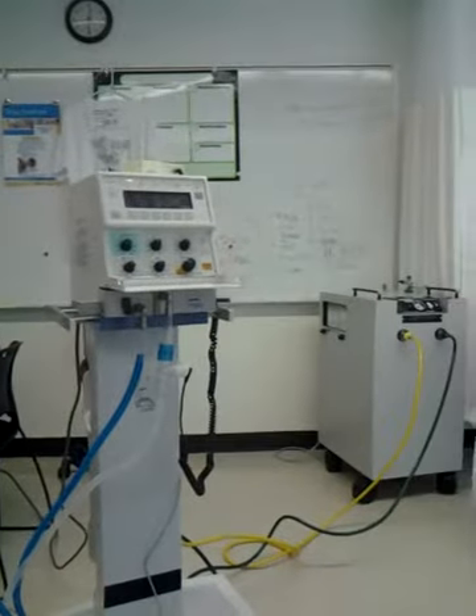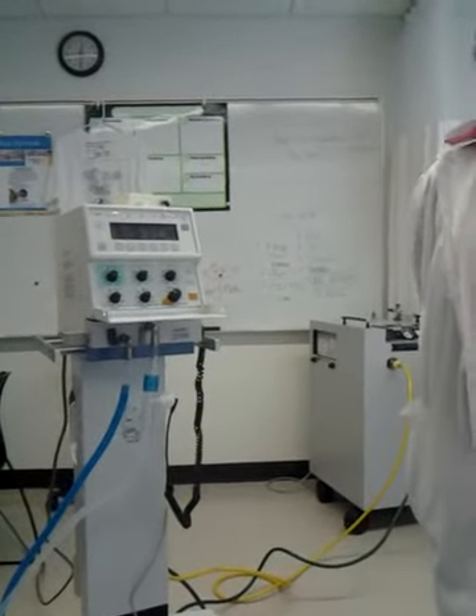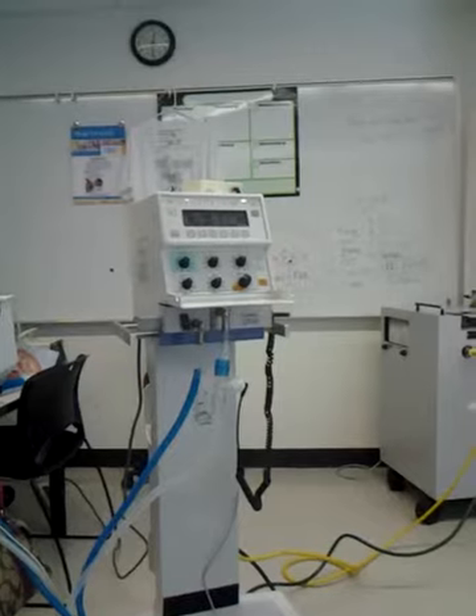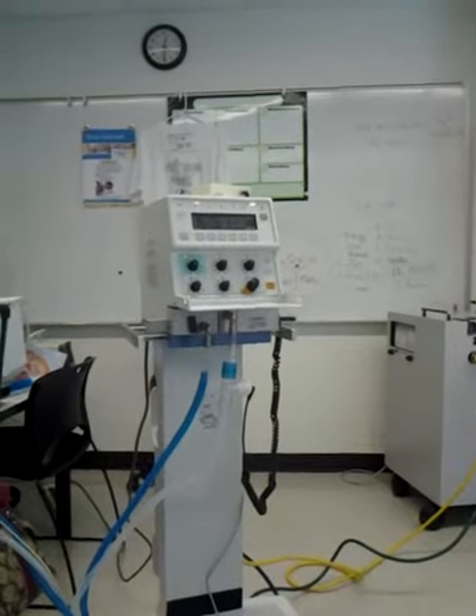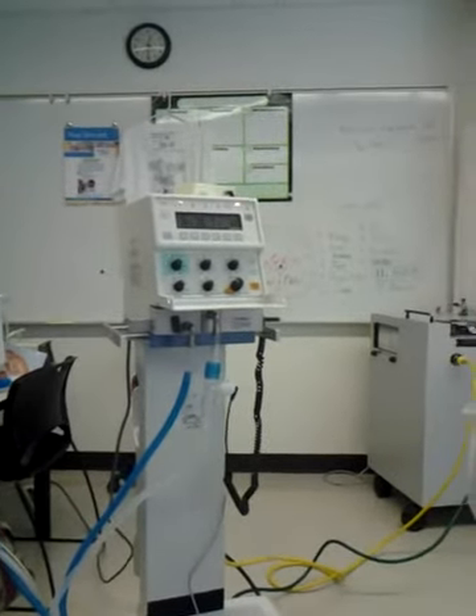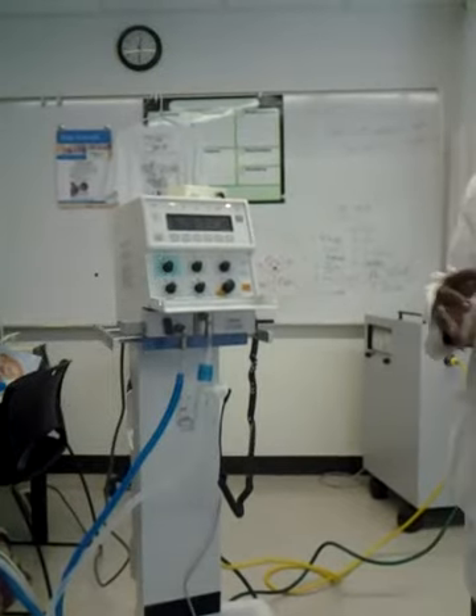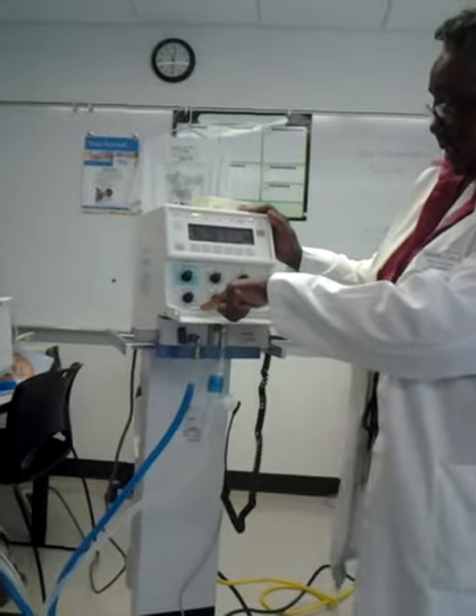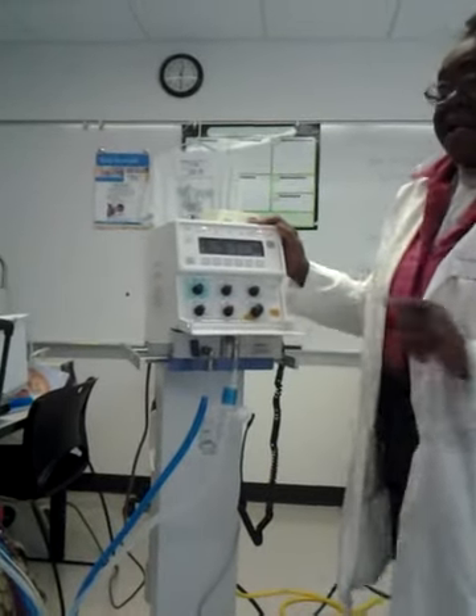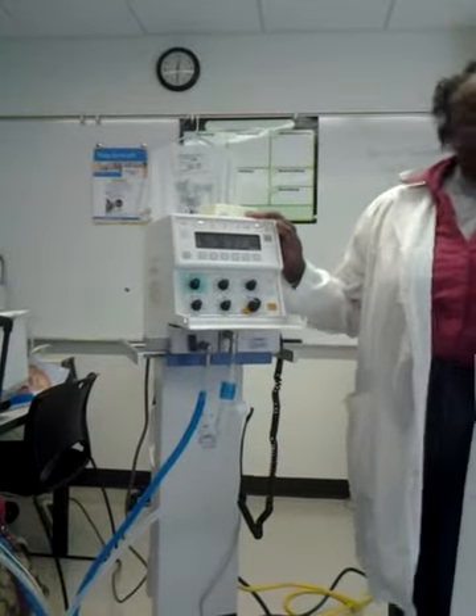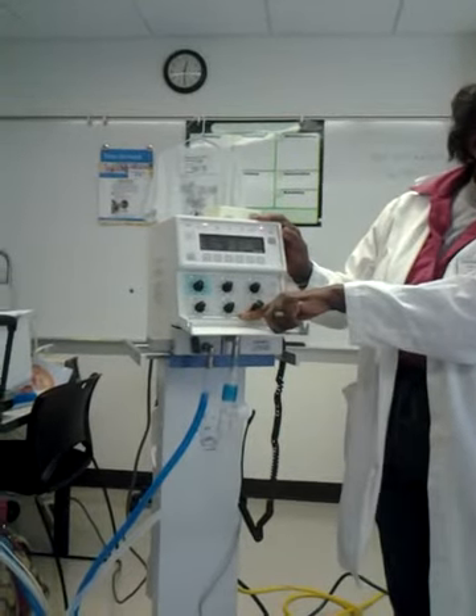4 to 10 liters per minute. 4 is very, very low, and that would have to be for like a micro preemie, somebody under a pound. Usually 8, 10, 12, depending on the size of the baby. Right now I have it on 10. And remember, you're doing pressure ventilation, so over here is your peak pressure.